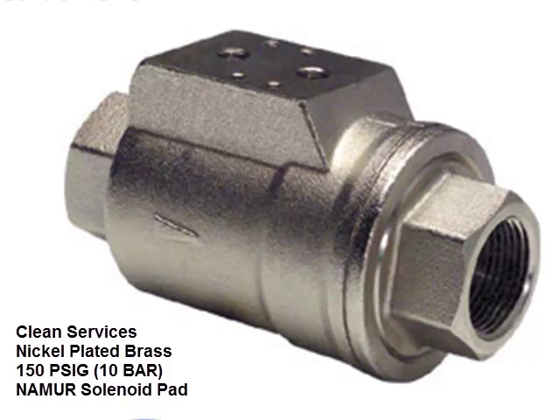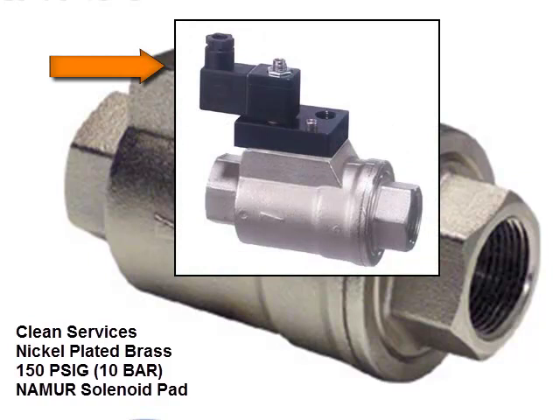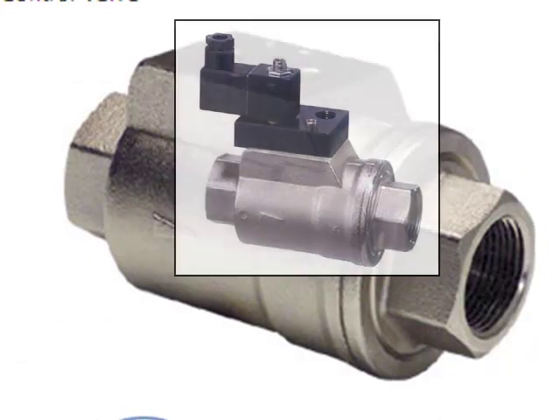The body and piston are nickel-plated brass. Seats and seals are available in Viton, which is standard, with EPDM and BUNA available on request. The pressure rating is 150 PSIG, or 10 bar. The body has a NAMUR mounting pad on top of the valve, which allows the direct mounting of NAMUR-style solenoid valves.